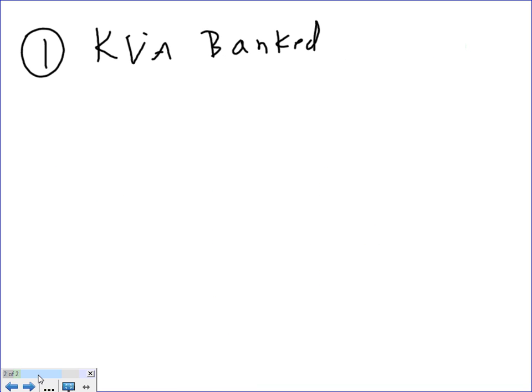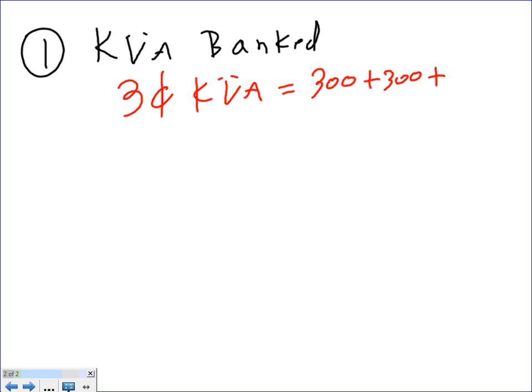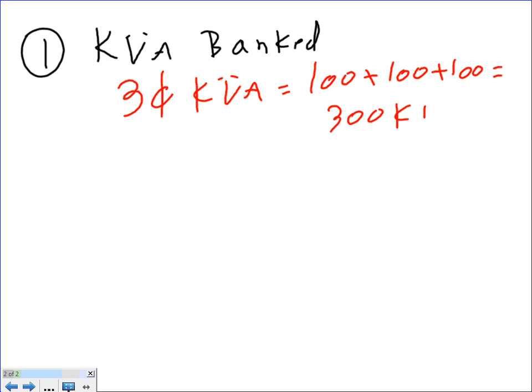we're going to do two types of banked kVAs. Number one is we're going to call it three-phase kVA. This one will be 100 from the first one, plus 100 from the second one, plus 100 from the third one, for a total of 300 kVA. So that's my three-phase kVA.